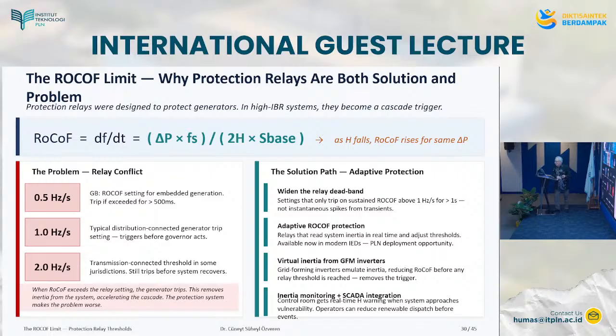And then also another technology is virtual inertia from grid forming inverters. These are also new technology, but are being implemented now. Grid forming inverters, they emulate inertia, reducing the rate of change of frequency before any relay threshold is reached, and that removes the trigger. And inertia monitoring plus SCADA integration. Control room gets real-time inertia warning when system approaches vulnerability. Operators can then reduce demand or dispatch, reduce the renewable dispatch and remove the low inertia generators from the system before such events. So there are possibilities and new technologies are coming in.